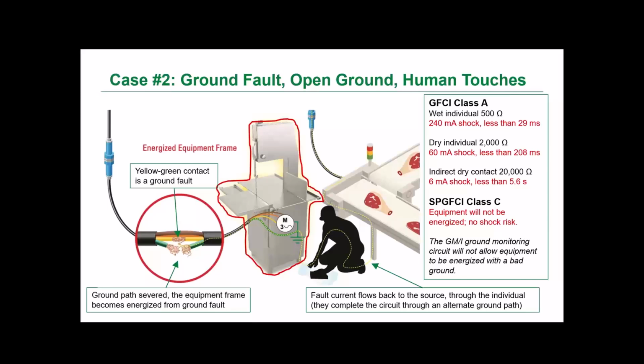For dry contact with a 2000 ohm body impedance, the shock could be about 60 milliamps, which would be interrupted within 208 milliseconds. And perhaps for a more indirect contact, looking at about 20,000 ohms as that body impedance model, the shock would be way down to about 6 milliamps and would be interrupted by the Class A GFCI in 5.6 seconds or less, which is the time off that inverse time curve.